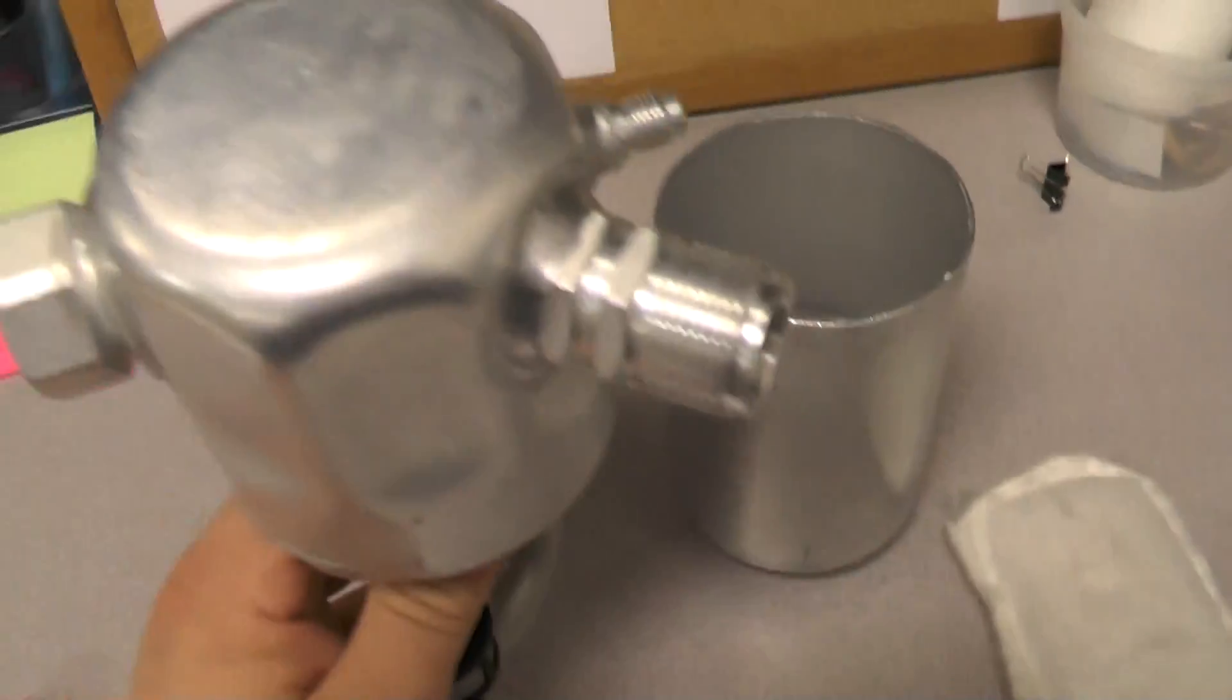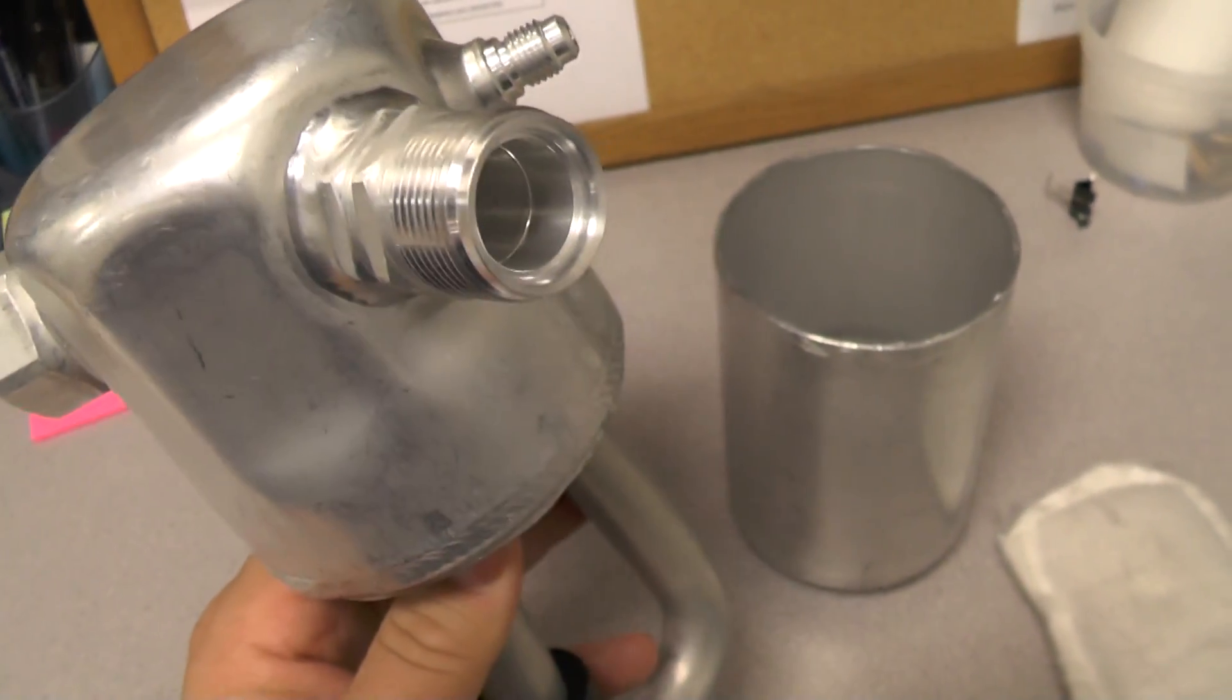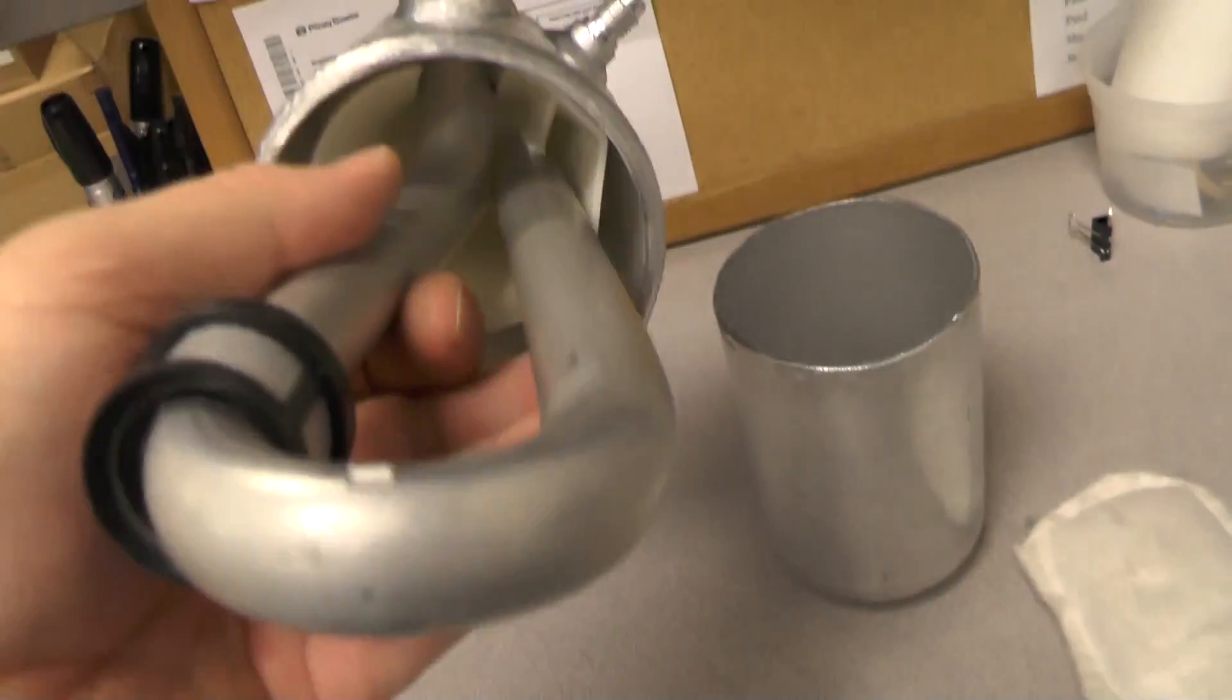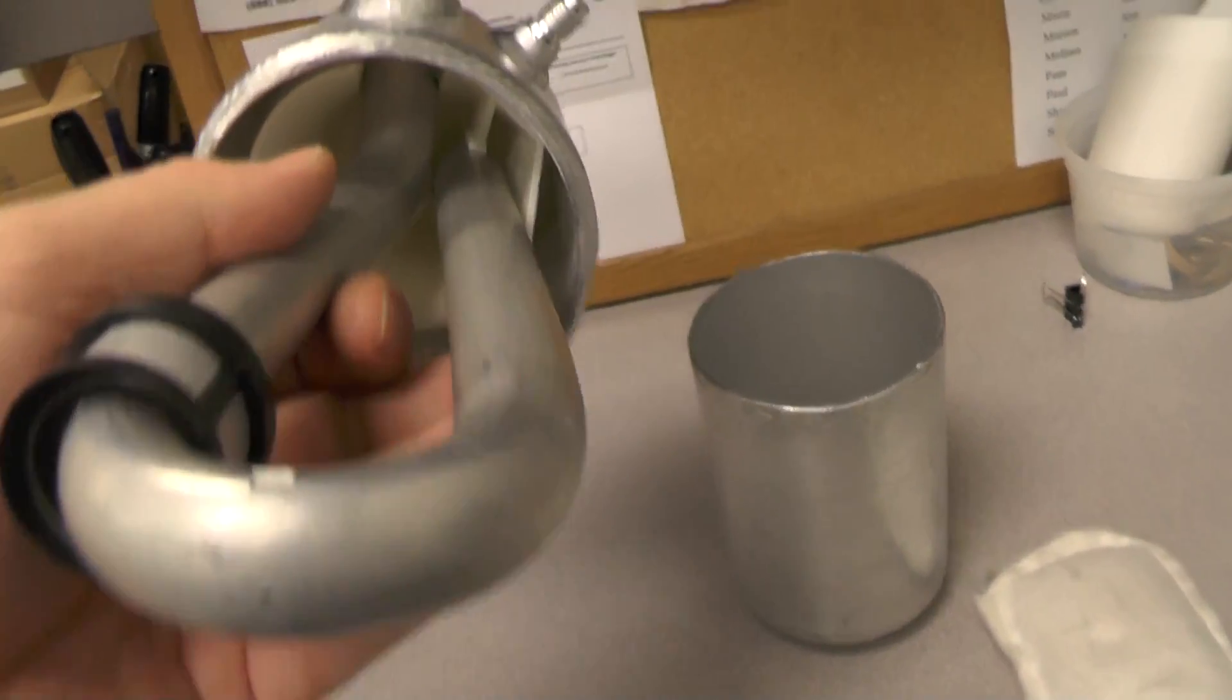So the way it works is the compressor is pulling refrigerant here on this output port. And you can see that the tube comes all the way down to the bottom to where this little hole is, and then goes all the way up into the top of that baffle plate.